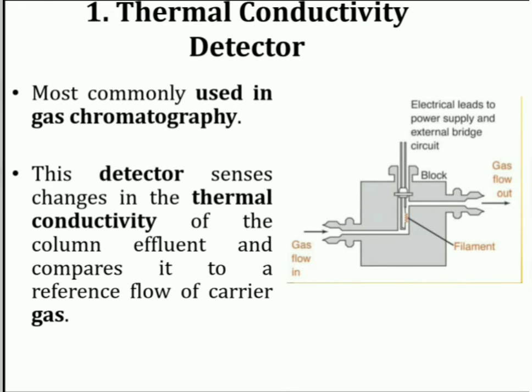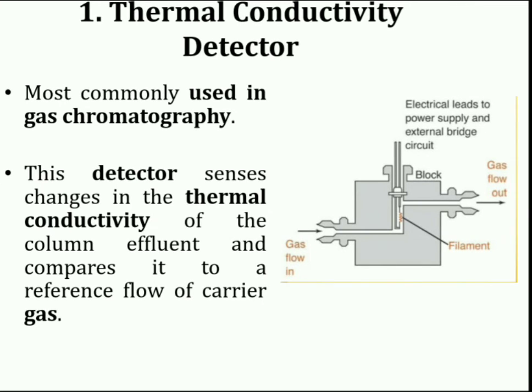Thermal conductivity detector. The thermal conductivity detector is universally used in gas chromatography but has moderate sensitivity. This detector senses changes in the thermal conductivity of the column effluent and compares it to a reference flow of carrier gas. This detector is based upon the alteration of the thermal conductivity of the carrier gas in the presence of an organic compound.